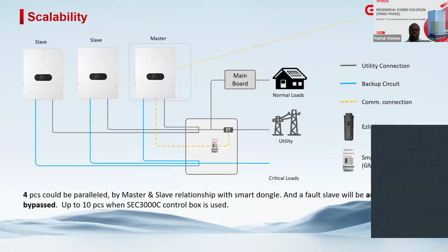Okay. This is, let me say, a single line diagram. So with the inverter, apart from now it's lacking the AC generator port, the most commonly used will be the on-grid port and the backup port. So with the KPLC or the grid line coming in, you branch out the power to the various inverters. For this, we have 3 inverters. So the KPLC coming in branches out to one of the inverters, then goes to the next, and the next. So that will be the on-grid port paralleling.